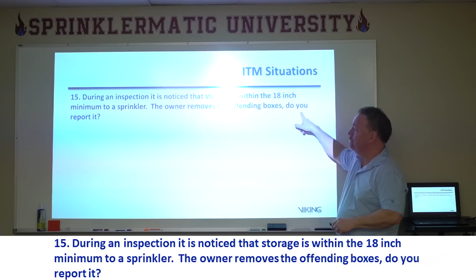So during an inspection, it is noticed that storage is within the 18-inch minimum of the sprinkler level. Remember from our previous session, we said that 18 inches was the minimum clearance you could have for storage to the sprinkler, in order for the spray pattern to develop. The owner removes the offending boxes. Do you report it? Do you cite it on your report that's what you found, or do you say, okay, great, I don't have to put that on the form?